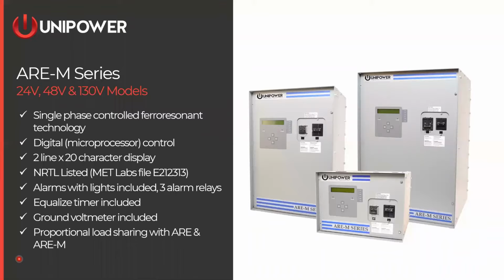Great, thank you, John. So the ARE-M series, while they do have a lot of optional features, there are a lot of things that do come standard. So obviously, this is a Ferro Resonant charger, so the output is controlled by a Ferro Resonant transformer and tunable tank circuit. It is controlled by a microprocessor, so the inputs are set on a microprocessor and then sent to that tank circuit for control. As John mentioned, has a 2-line by 20 character display on all units, and they're all listed to MetLab's E212313. So every one of these is NRTL listed.